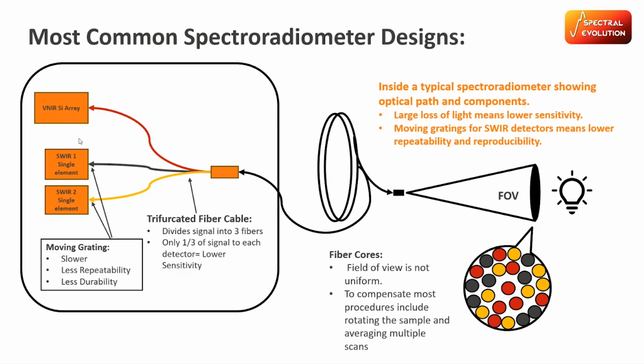The other thing that does is it makes your field of view non-uniform. So oftentimes with older spectrometers, there's the necessity for taking more than one sample and averaging them together by rotating your sample 90 degrees or rotating your fiber 90 degrees to account for the fact that the fibers are not uniform.